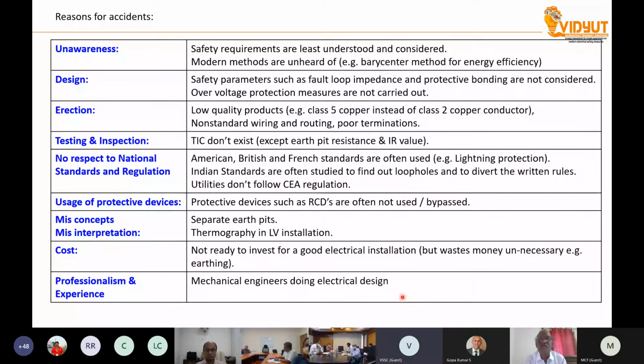Especially the fault loop impedance is not at all measured during the initial, before the initial commissioning process.